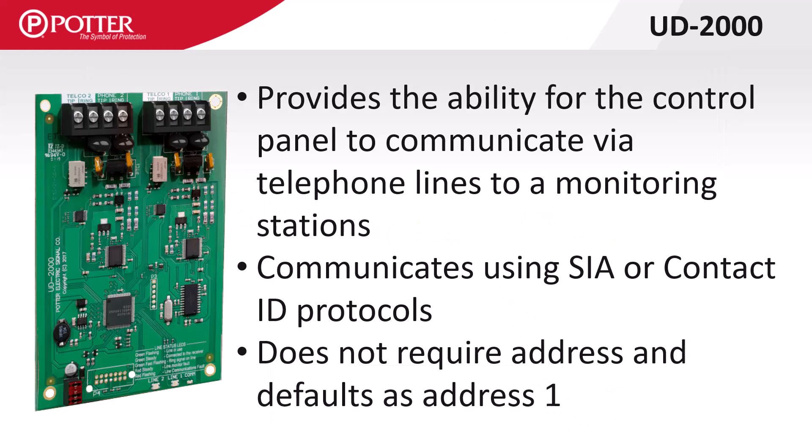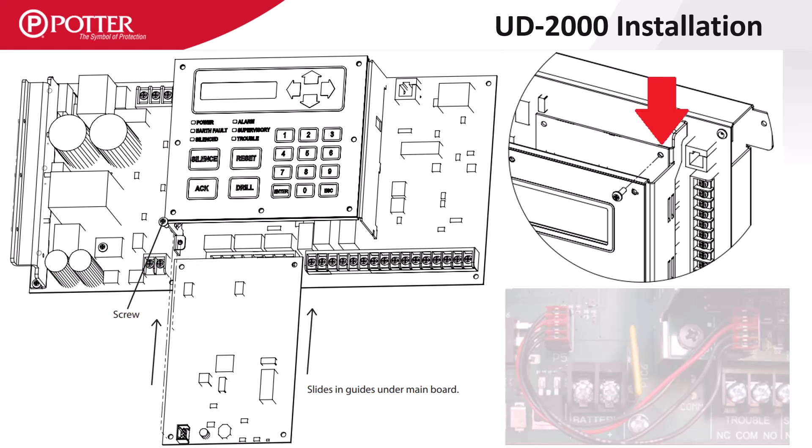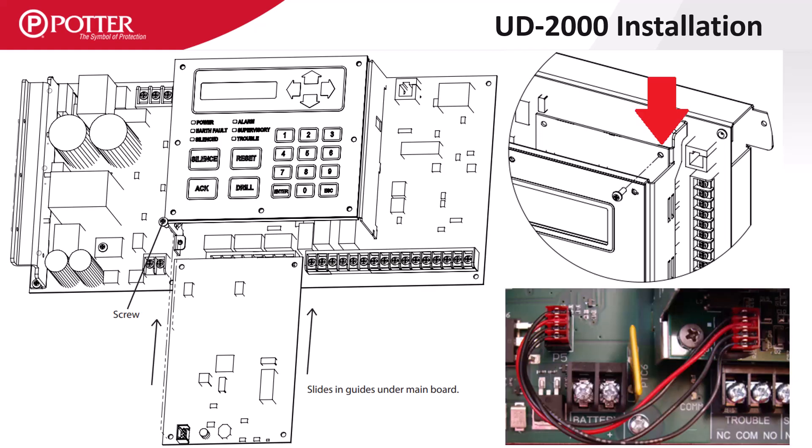The UD2000 DACT is an optional accessory card added for central station reporting via phone lines. This card requires no addressing since only one can be installed on a control panel. The UD2000, as well as the panel's built-in IP communicator, support Contact ID and SIA formats. The UD2000 slides in behind the built-in annunciator on the control panel with guides to hold it in place, is secured with a screw, and uses a 4-pin cable to plug the DACT card into the control panel.